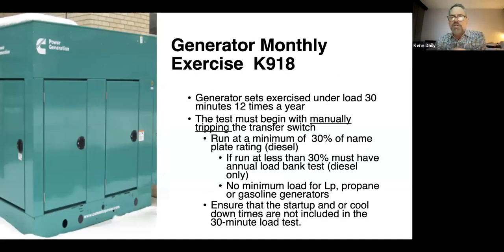You run it under load once a month. A loaded exercise is where you take it from pole power of your building to generator power. You're manually tripping the power, manually tripping the transfer switch. You can't be on a timer to count this. So you can't count a power outage as a monthly test either, because that's not a manual trip. A manual trip is where you do it. You push the button or you manually trip the transfer switch.